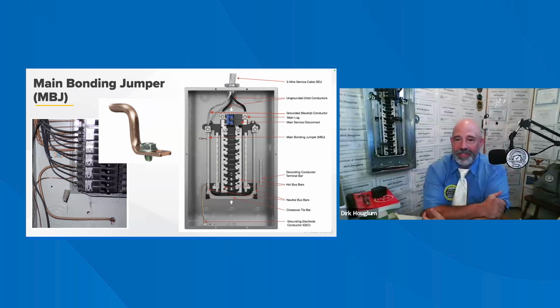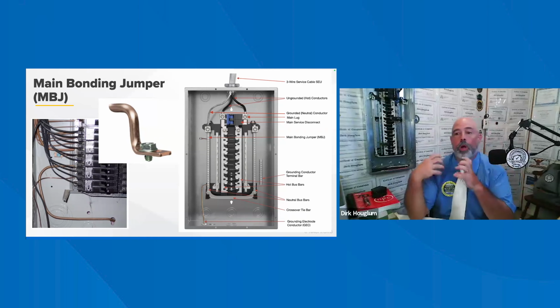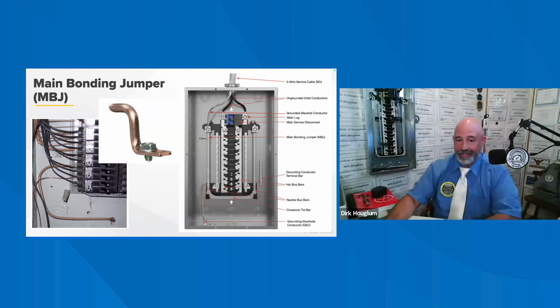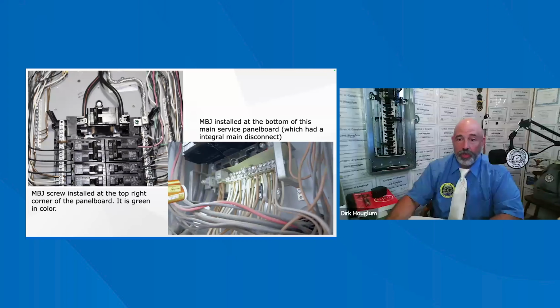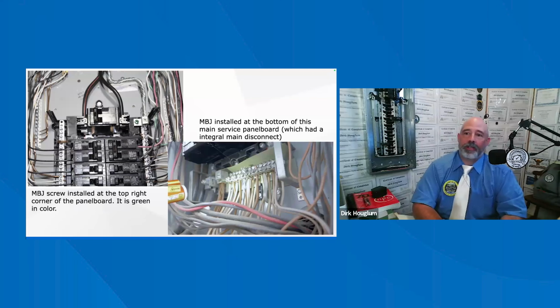Anyways, the MBJ ties everything together. It connects the neutral and the grounding system, so it includes the bare or copper ground wires at the service panel to itself. The connection keeps all parts at the same electrical potential, helping ensure the system's safe and grounded. So it's going to send overcurrent somewhere else. The factory supply bonding jumper strap or screw is shipped directly as loose components because the manufacturer doesn't know how the panel will be used.